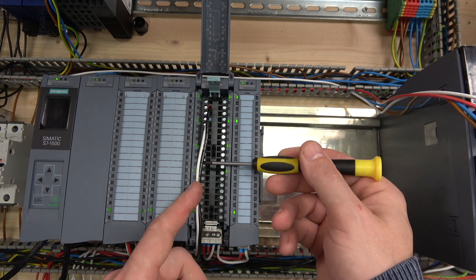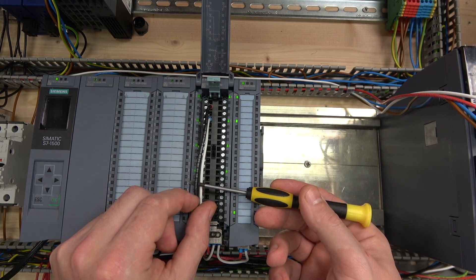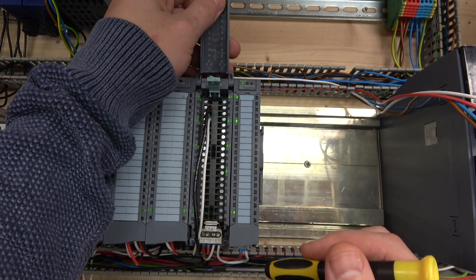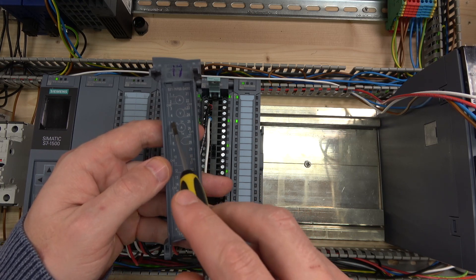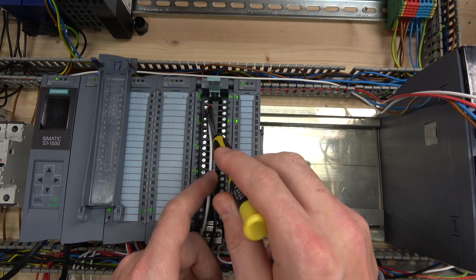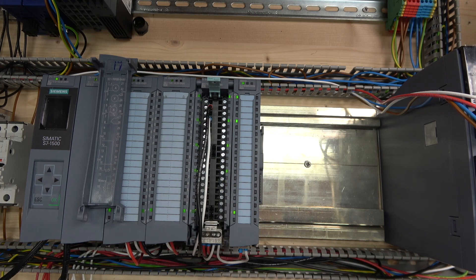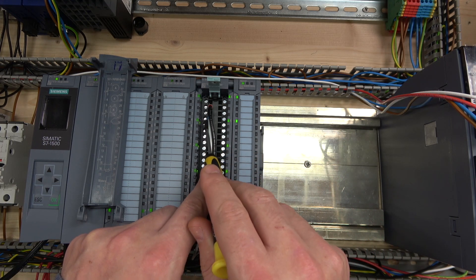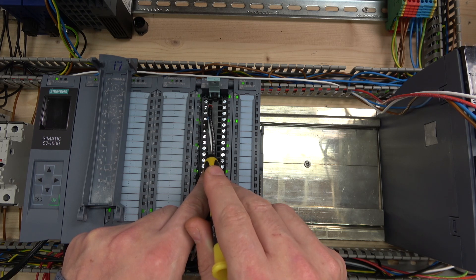When it comes to wiring, this black cable is the returning signal from the sensor — the analog cable coming from the sensor — and that goes into terminal two. My sensor is a four-wire type, so as I explained, we are using terminals two and four. My plus signal comes into terminal two from the sensor, and my negative goes into terminal four — which actually comes straight from my main power supply, because my sensor is receiving power and the negative must come from the same negative the sensor is receiving.